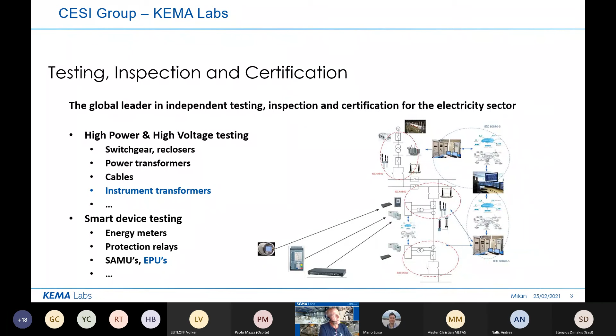I will focus a little bit on instrument transformers, otherwise I could give a presentation of all day, and I'm limited to 5 to 10 minutes, so let me try to do that. So what are our current activities up to now? We did, of course, a lot of type testing of conventional instrument transformers, according to nowadays the 61869 series of standards. We have seen them coming by before. And that includes all the different testing that I mentioned in those standards as partly listed in the table below. They don't cover everything, but it's almost there.